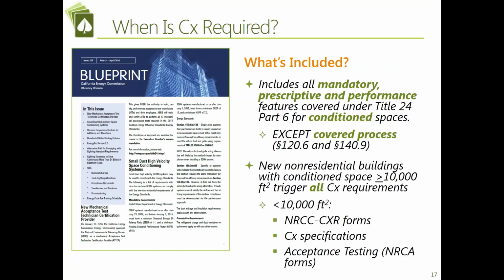The triggers for commissioning are design review, commissioning specifications, and that acceptance testing that has to be happening for every building type will be triggered for all brand new buildings, no matter how big they are. Now, what I like to call the full flavors of commissioning, which we'll be going through, not only will you trigger commissioning design review, these NRCC CXR forms, commissioning specifications, and acceptance testing, you'll also trigger everything else, is when that non-residential occupancy of conditioned space is equal or greater than 10,000 square feet. Less than 10,000, design review, commissioning specs, acceptance testing. Equal and greater than 10,000 square feet of conditioned space, everything.